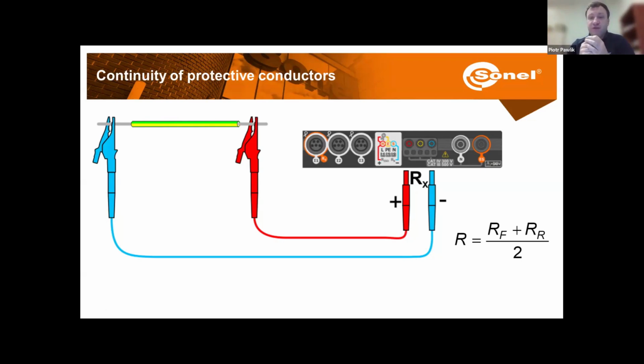So before that test, we need to remember to auto-zero the test leads. Then the meter will calculate the resistance of the test leads themselves and deduct them from the overall result, giving us just the result of the part of the wire that we want to check. And here we need to check this continuity with forward current flow, with the reverse current flow, and the average of that will be our result.